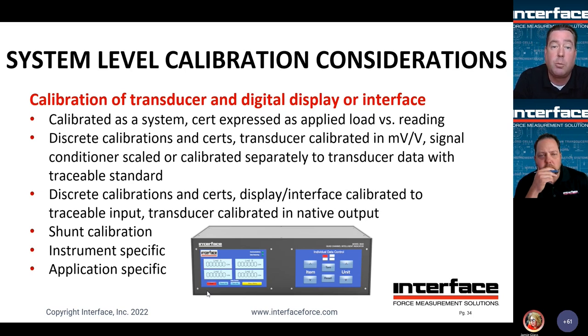You can also do traceable calibrations and certs with the display interface calibrated to a traceable input. This example would be if we, for instance, had the load cell calibration. Let's say we did an E4 calibration on a load cell in millivolts per volt, and we had, in this instance, a display that we could calibrate in millivolts per volt separately, or we used a CX box to essentially define how the indicator is reading a millivolt per volt input, and then provide a cert for that. So you have two separate traceable certs.